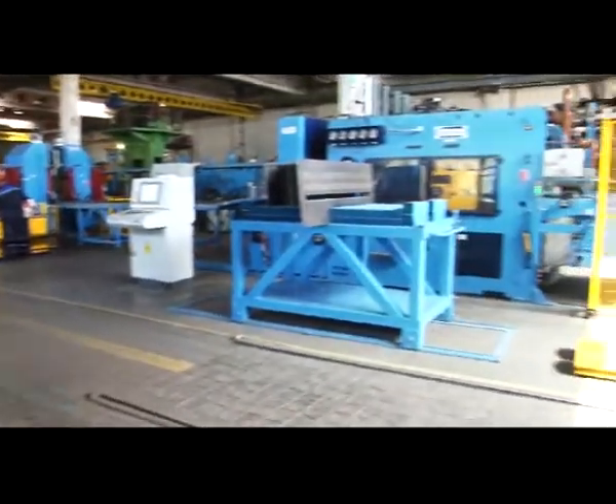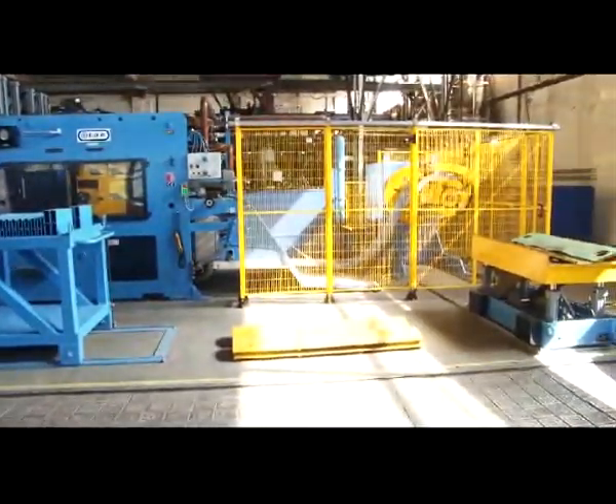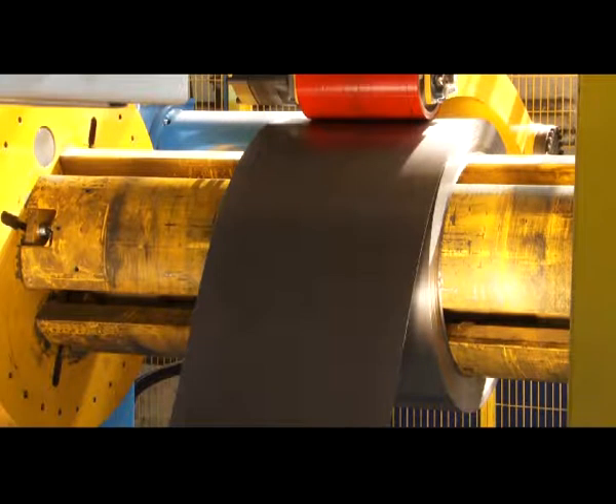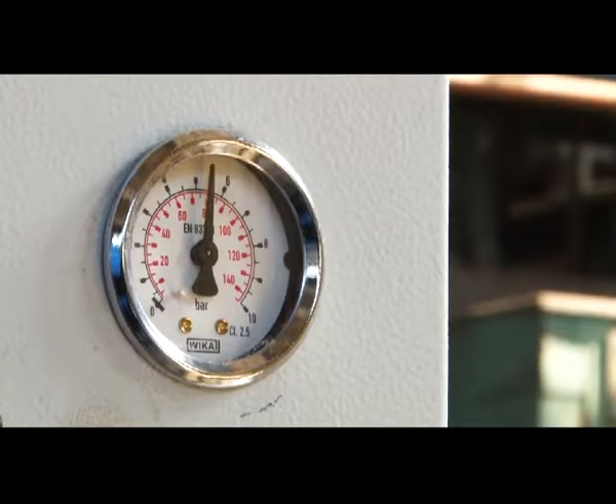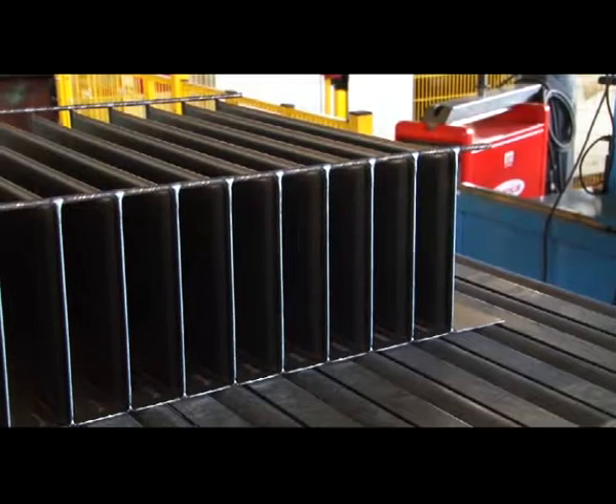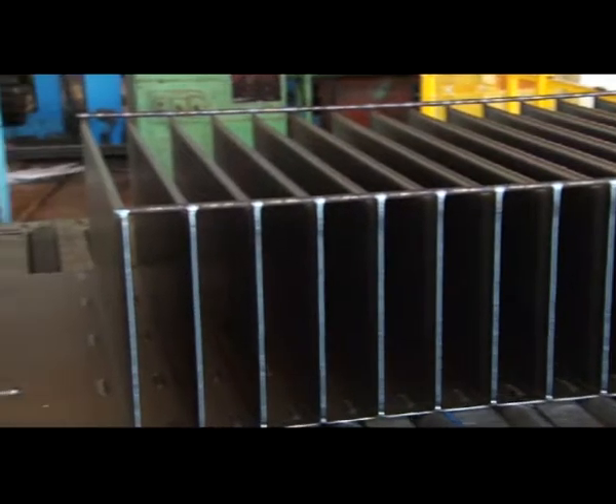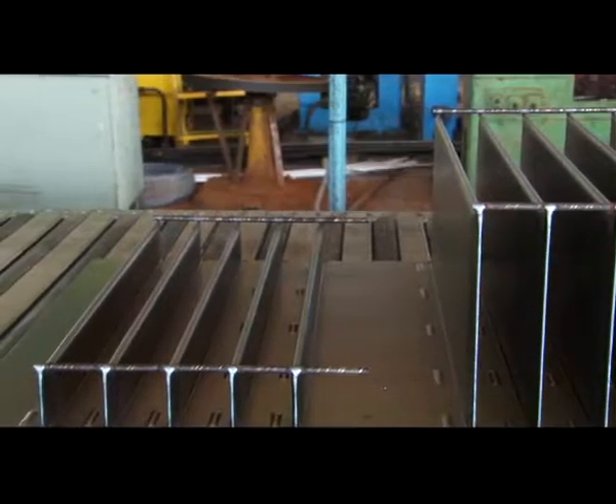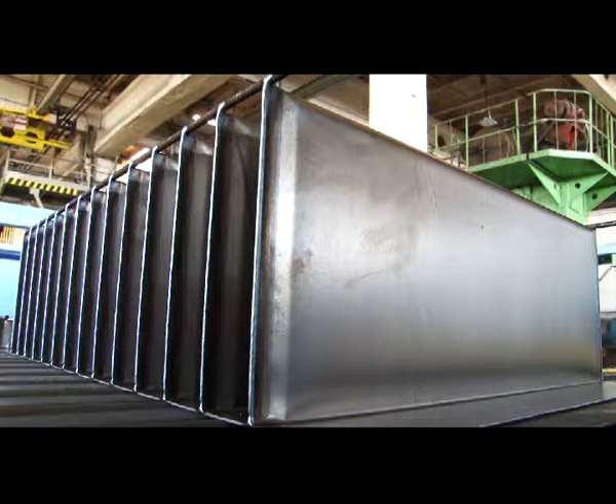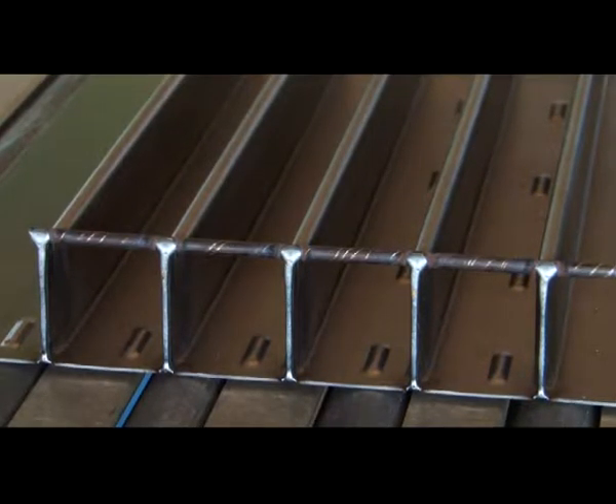A roll of steel is set up on a special device, a recoiler, and then the machine is turned on, which bends the sheets of steel in a way so as to create a corrugated wall. Because of its shape, when the transformer is used, the warmed-up oil will stretch the steel but will not tear apart the places where it was welded. This ensures a high level of safety of transformers.